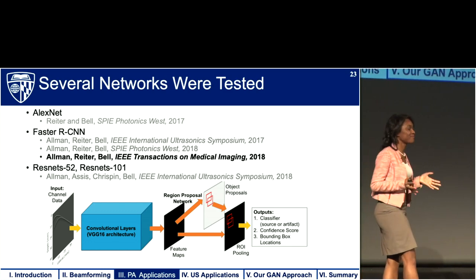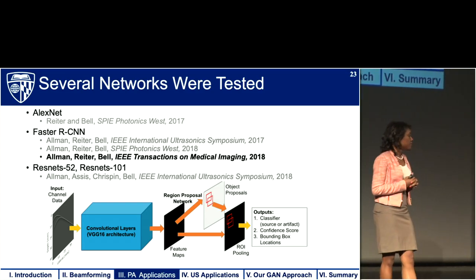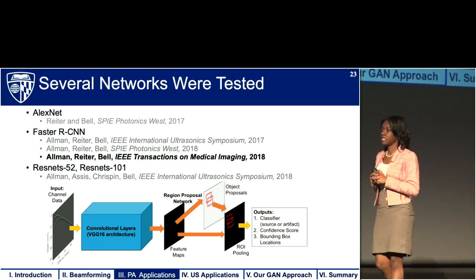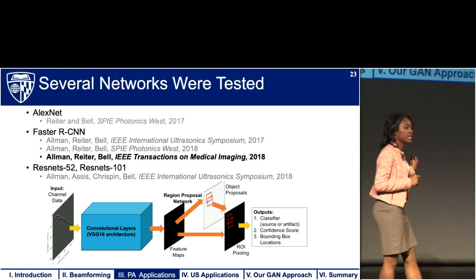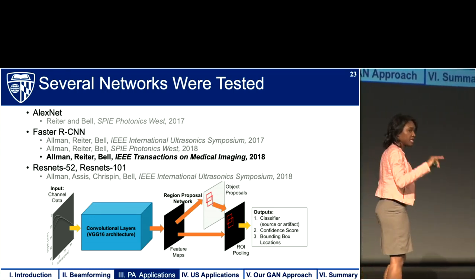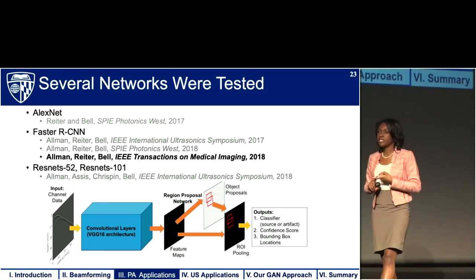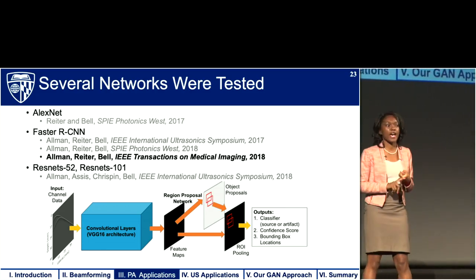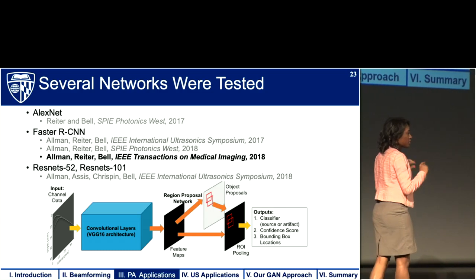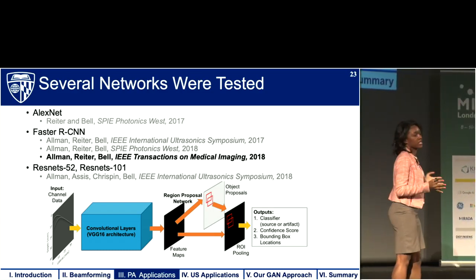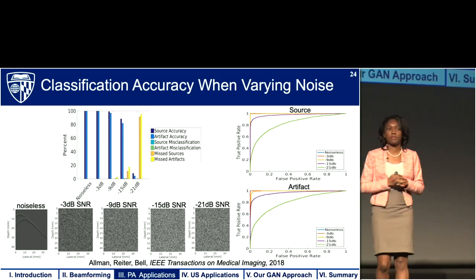Deep learning is not an exact science, so it required some trial and error, and several networks were tested. The one we settled on and published last year is the Faster RCNN network, published in IEEE Transactions on Medical Imaging. The network architecture inputs raw channel data sensed by the ultrasound transducer — first in simulation for training — and has three outputs of interest: first, a classification of the detected wavefront as a source or an artifact; second, a bounding box location telling us where the detected source or artifact is located; and third, a confidence score about the detection.